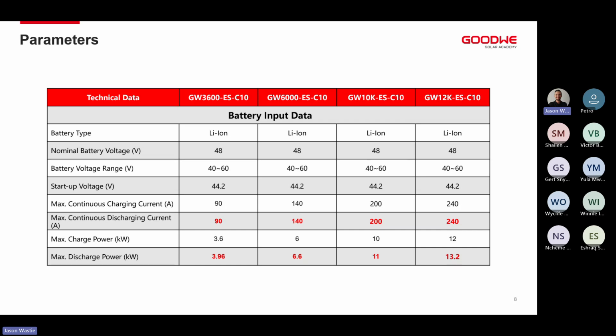Then next is the maximum charge and discharge power. All of the inverters within the ES Uniq range can discharge at 10% higher than their nameplate capacity. So on the 12 kilowatt unit, 13.2 kilowatts. On the 6 kilowatt unit, 6.6 kilowatts. This is a permanent discharge. Again, this is determined by what the battery can or cannot do, or what the BMS allows the battery to do.